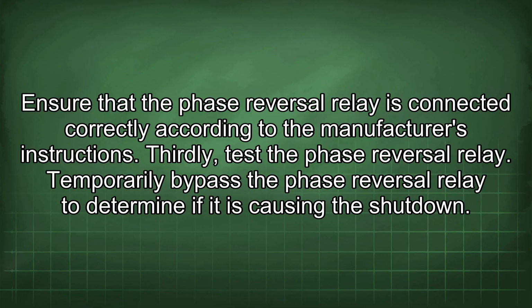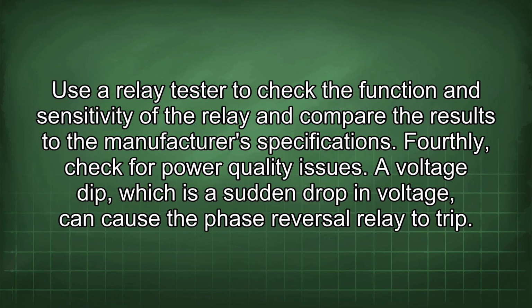Thirdly, test the phase reversal relay. Temporarily bypass the phase reversal relay to determine if it is causing the shutdown. Use a relay tester to check the function and sensitivity of the relay and compare the results to the manufacturer's specifications.